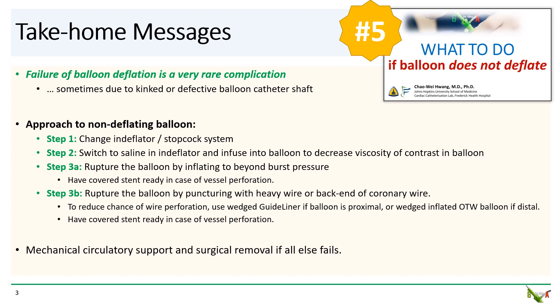Step 3a: try to rupture the balloon by inflating it beyond burst pressure. Usually more than 30 atmospheres are required, and obviously have a covered stent ready in case of vessel perforation. Step 3b: try puncturing the balloon with a stiff wire or the back end of a coronary wire. Remember to use a guideliner or an inflated OTW balloon to minimize the chance of wire perforation. Finally, if all else fails, you'll need to put in mechanical circulatory support and call for surgical removal.